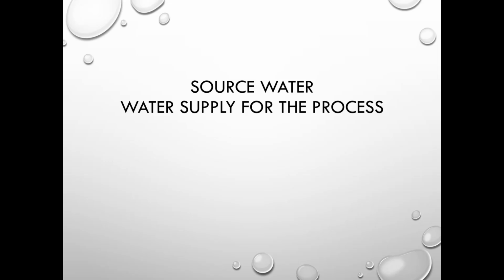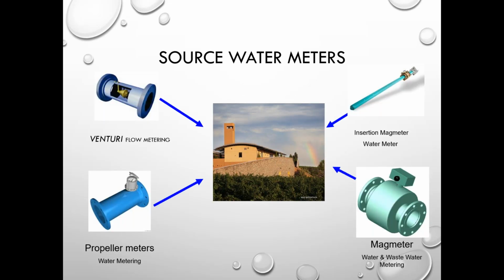So source water, when I talk about source water, it's hard for me to say clean water because sometimes people are pulling from rivers and streams and it may not be treated, but it's a source water to their facility, right? So we've got two different animals when you talk about flow meters to the facility. One is your source water meter, which is coming to the facility generally in a closed pipe. So it's not open to the environment. It's treated, right, and it comes to your facility all nice and clean in a closed application. So you're talking about generally full pipe flow meters.